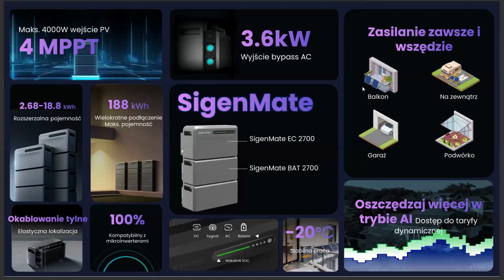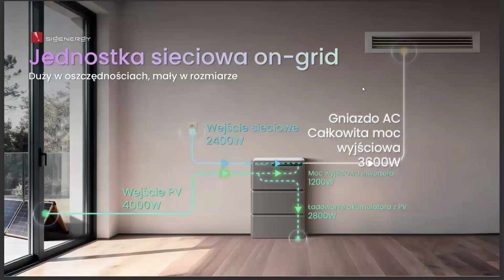2. Price arbitrage in apartments, zero export. This is an ideal solution for apartments, where exporting energy to the grid is often not permitted. Our system has been tested for price arbitrage in zero export mode. How does it work? The customer charges the battery from the grid during low price periods, e.g., G12 tariff or dynamic pricing, stores the energy, and then uses it for self-consumption when electricity prices are highest.